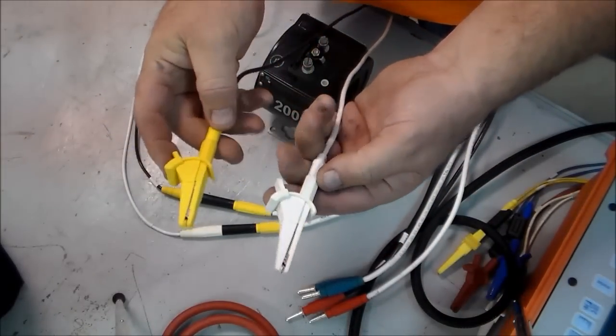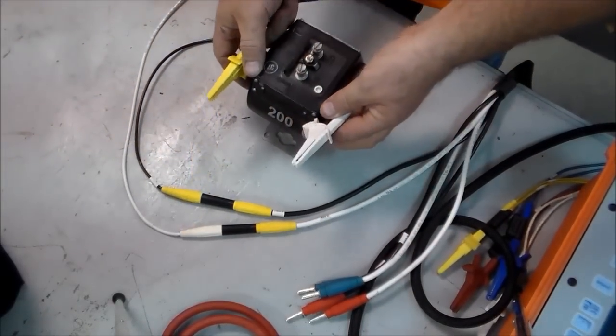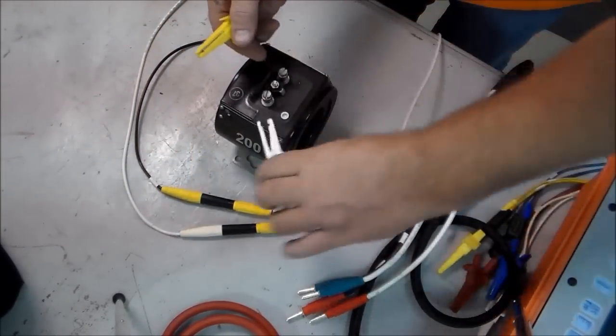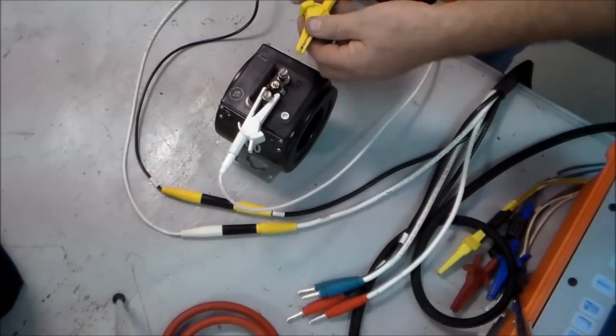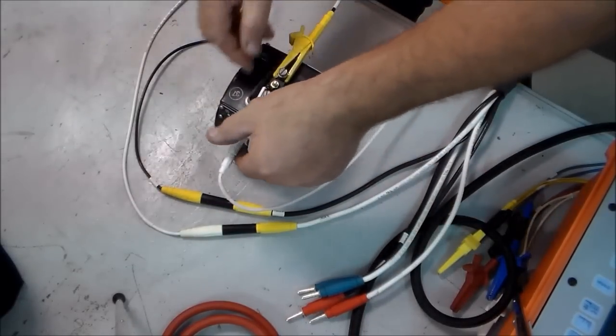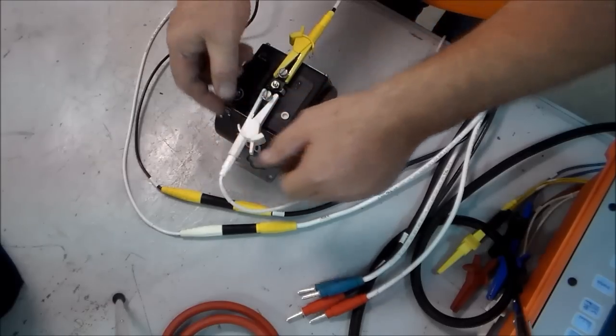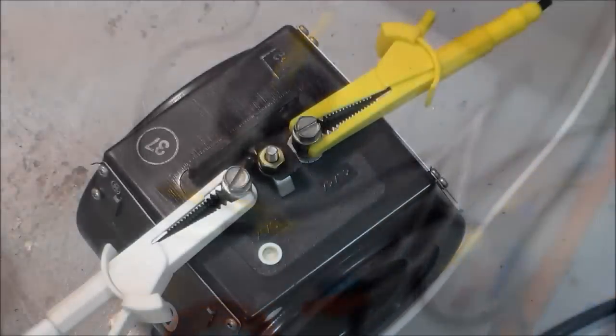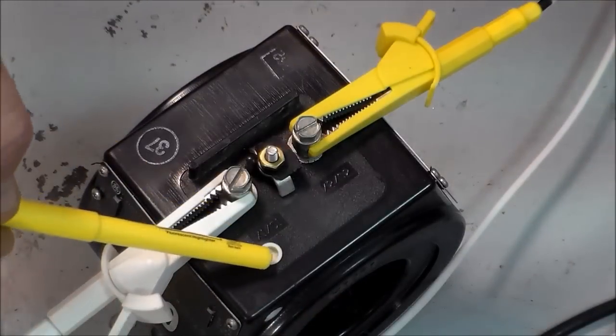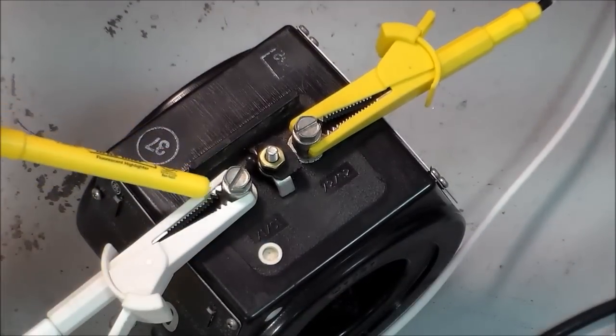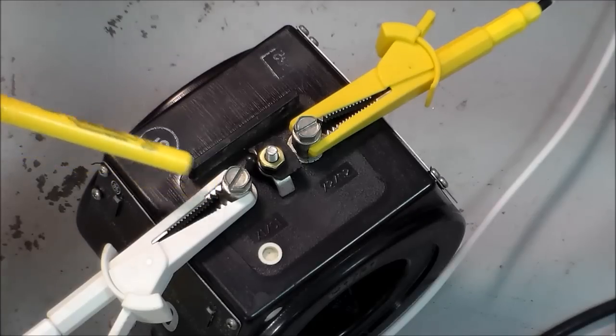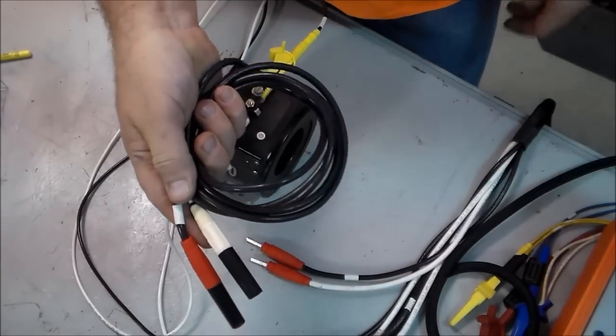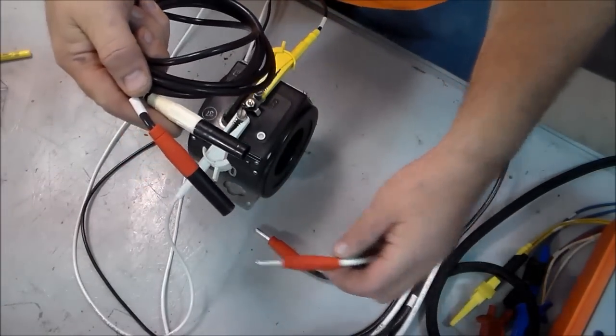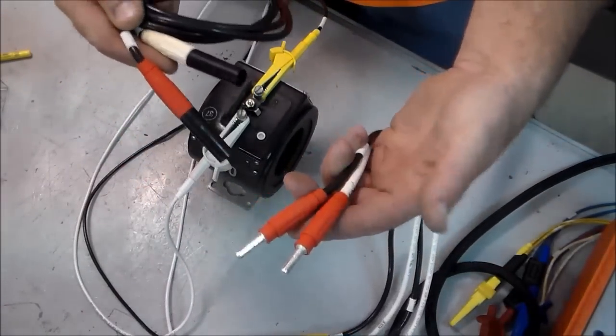Connect your alligator clips to your secondary terminals. The white clip goes to the polarity mark. Make sure the CT is unshorted and the clips aren't touching the shorting bar. Now get your drive cable, and at first we're only going to hook up the lead labeled drive.